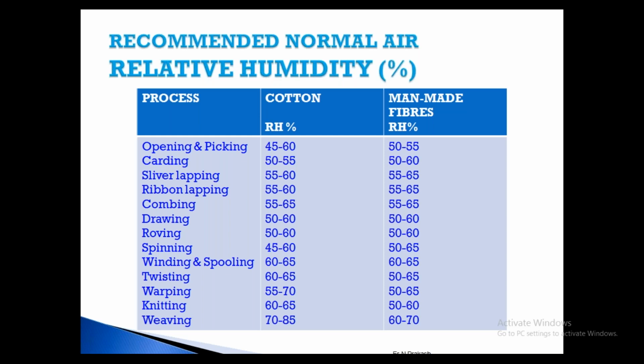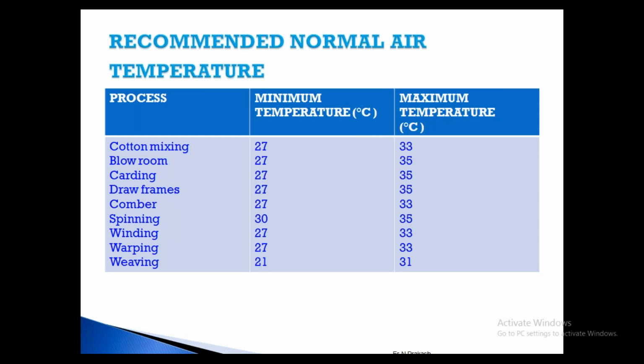This is about relative humidity. In the same way we have it for temperature also. Minimum temperature has to be maintained at various processes, right from blow room to carding, spinning. So 27 degrees is the minimum temperature. Maximum temperature is 33 degrees centigrade for the cotton mixing, and for spinning it can go up to 35. Like that, norms and recommended temperatures are there. If you operate within that, you will get the required quality, productivity, everything.